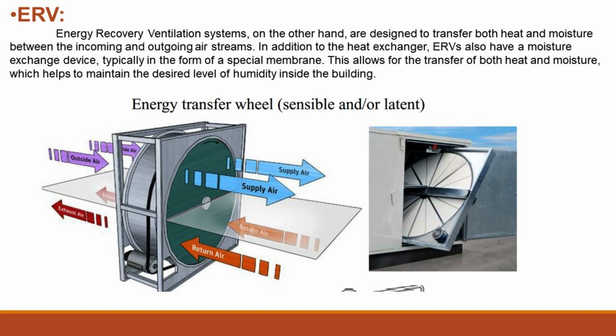ERV, energy recovery ventilation systems, on the other hand, are designed to transfer both heat and moisture between the incoming and outgoing air streams. In addition to the heat exchanger, ERVs also have a moisture exchange device, typically in the form of a special membrane.